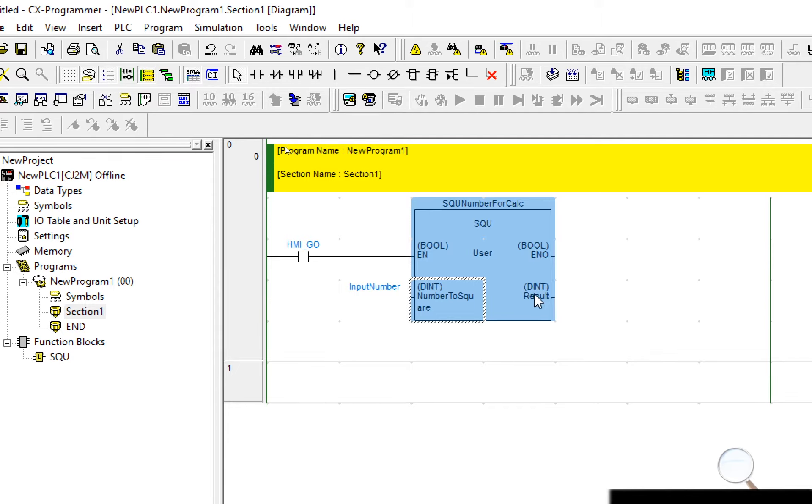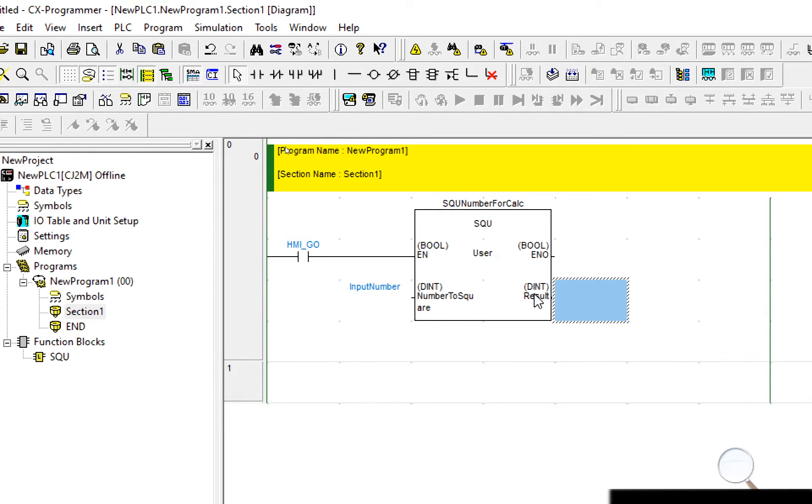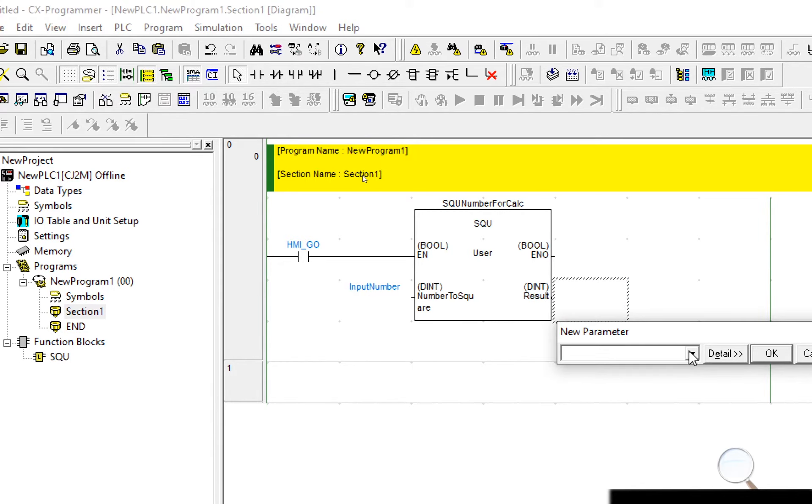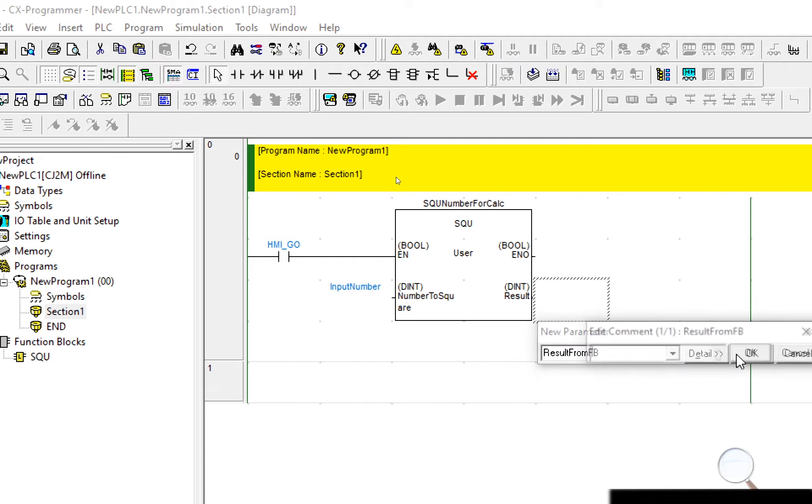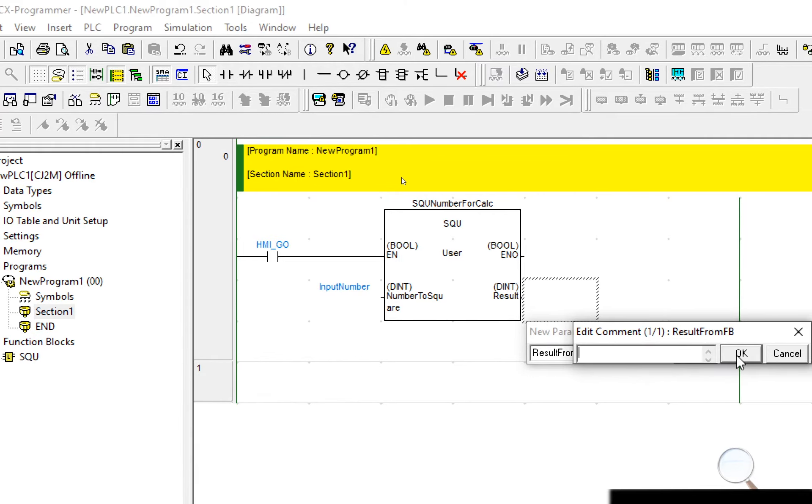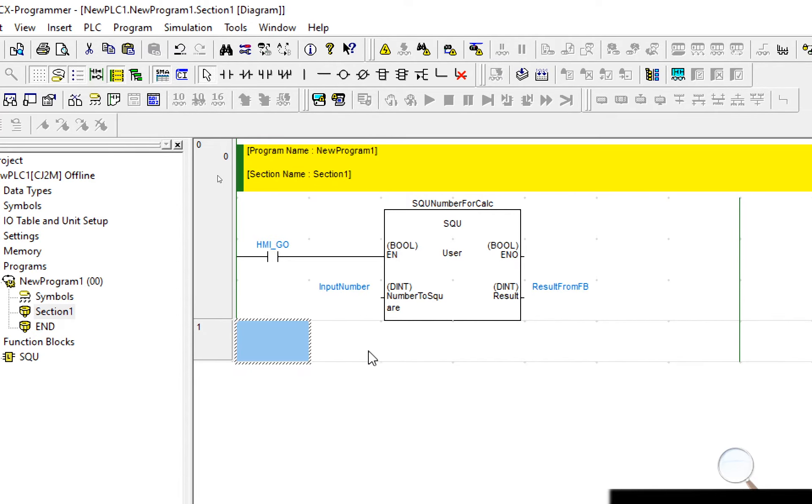You can see now that the input number parameter is now assigned to that particular input. For the output I'll do the same, select the output I want, take one step to the right in this case, select enter and select the output. And I'm done, my function block is now completed and I've got no red lines here to say there's an error on the rung.